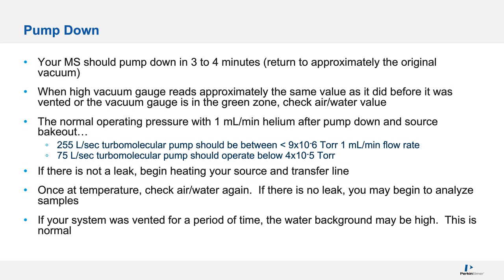I usually keep the source at a temperature of 50 degrees while I'm doing this. I do a leak check. If my water is higher than my nitrogen, I start heating up the zones. Now the water is going to go high because you're burning off water at this point. That's fine, it's normal. Water is more difficult to pump than air, so it hangs around longer. The water's not doing the harm to your mass spec. It's the oxygen that's there.